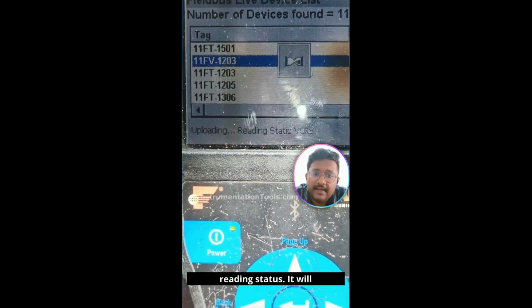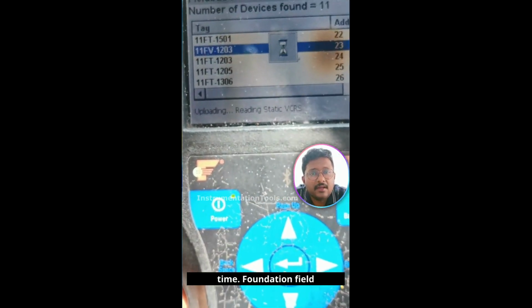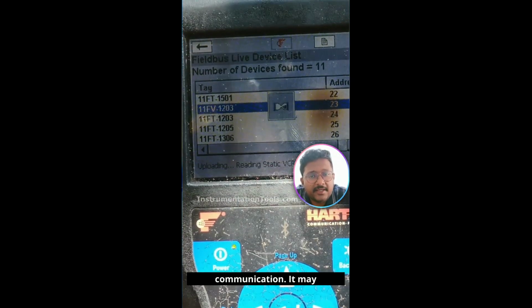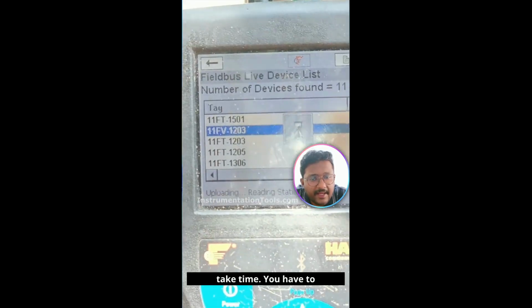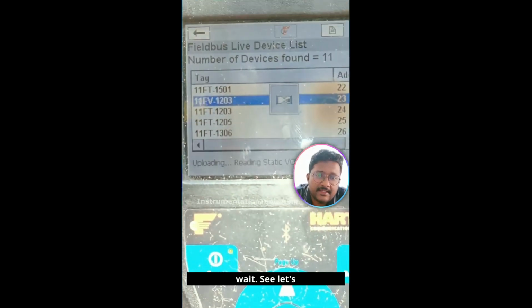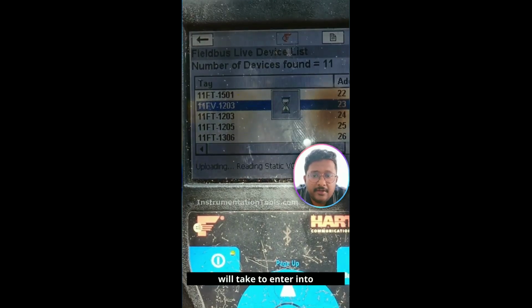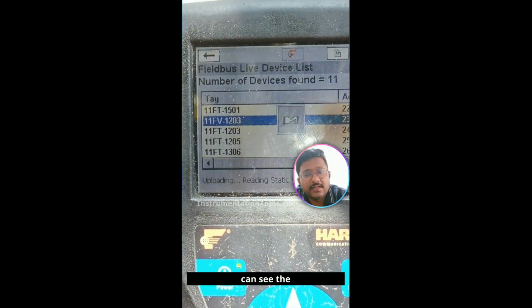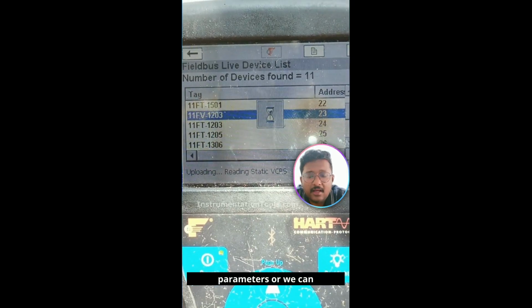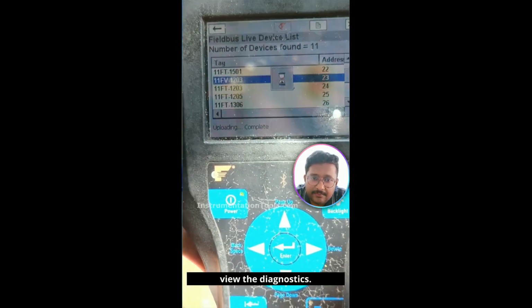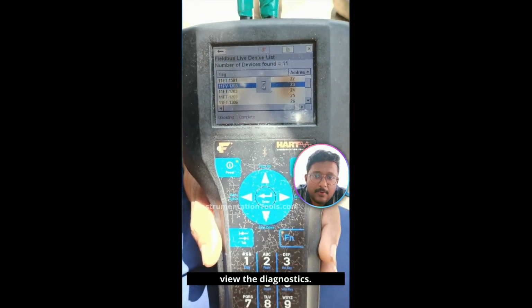See, uploading a reading status. It will take time. Foundation Fieldbus uses acyclic communication here, so you have to wait. Let's see how much time it will take to enter into the device so that we can see the configuration parameters or view the diagnostics. Loading complete.